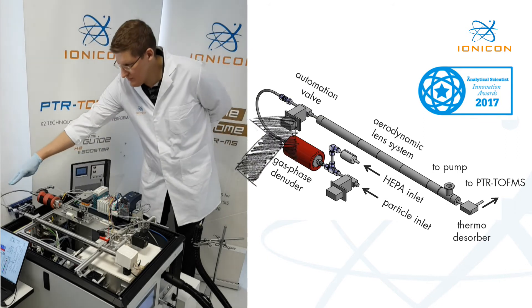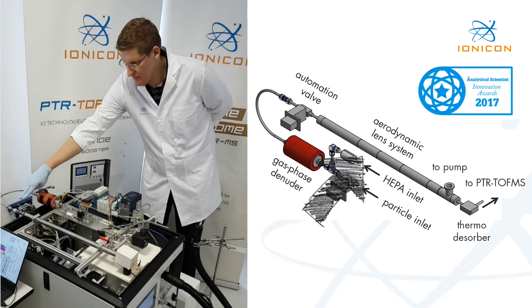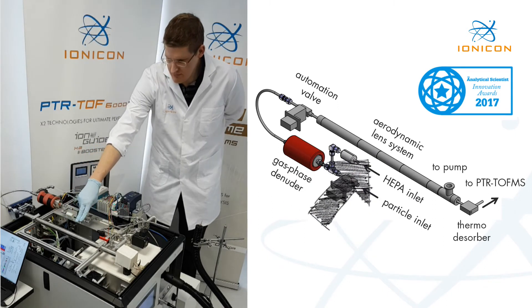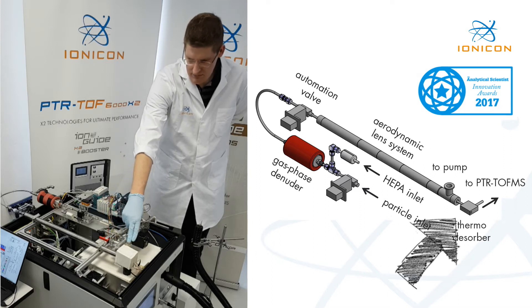After a soft U-turn, the sample passes through a critical orifice and is accelerated into our high-pressure aerodynamic lens system. At pressures in the range of a few millibars, particles are collimated in the center of the aerodynamic lens system and are subsampled by a virtual impactor. Finally, the thermodesorber evaporates the particulate organics at moderate temperatures around 140 degrees Celsius and reduced pressures, and guides the newly formed volatiles into our PTR-TOF-MS for analysis.